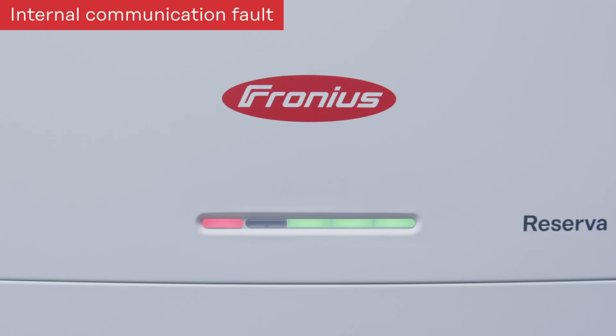Furthermore, when it comes to data communication, we also have error codes for the internal as well as for the external communication fault. So this LED status will show you the internal communication fault. So that means that you have either a communication error between the modules that are stacked in series, or you have an internal communication error between multiple Reserva towers. That means for the parallel connection, you will also get this internal communication fault.